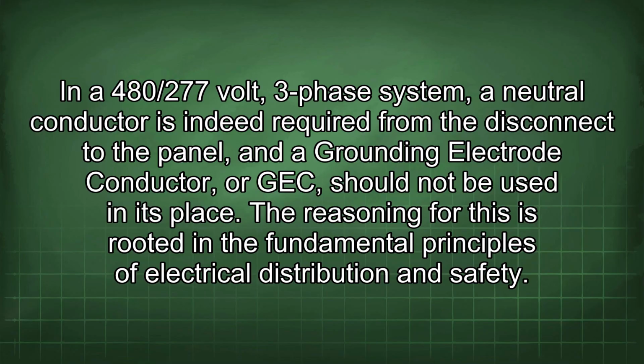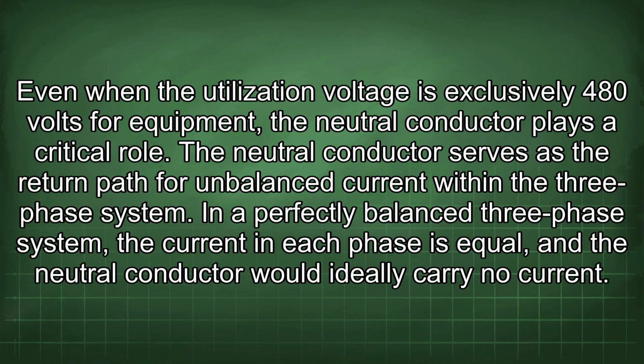In a 480/277 volt three-phase system, a neutral conductor is indeed required from the disconnect to the panel, and a grounding electrode conductor, or GEC, should not be used in its place. The reasoning for this is rooted in the fundamental principles of electrical distribution and safety. Even when the utilization voltage is exclusively 480 volts for equipment, the neutral conductor plays a critical role.